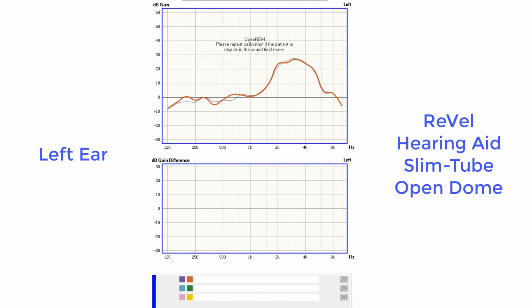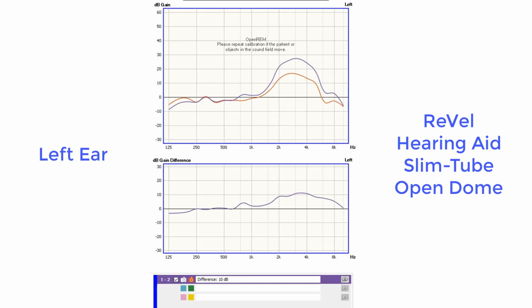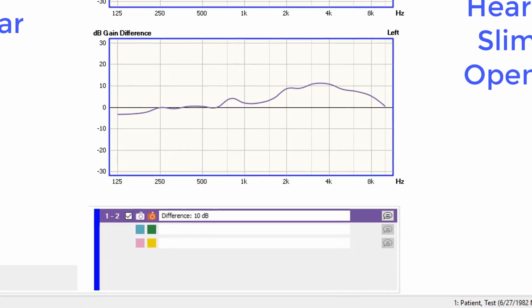And let's go ahead and test the left ear that we have the slim tube and open dome on. And as you can see here, again, we're looking for that red line to drop further away from that purple line, which indicates to us that we are having measurable noise reduction happening with this hearing aid when we're playing noise to the hearing aid. And we can see that there is a 10 decibel reduction in noise with the slim tube and open dome, which is also very good.